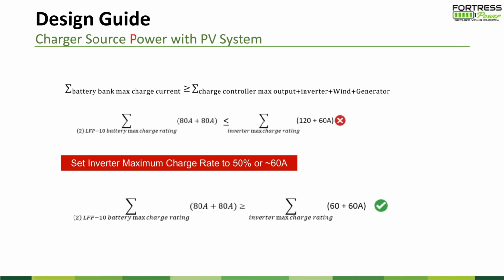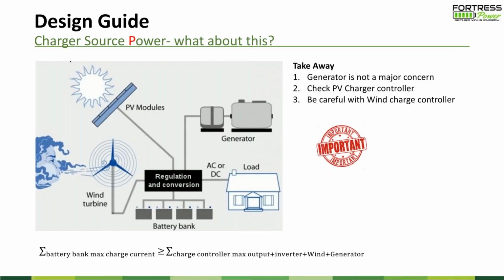Let's come to the next slide. There is something out of the ordinary. If the customer has a wind turbine, has a generator, has a PV system, and has something else, they all want to charge the batteries. It's not a big concern if you regulate everything with one inverter. For example, your PV goes with the inverter and the generator also goes with the inverter. Most inverters support complicated configuration for when to use what, so it's not a big concern for the battery.